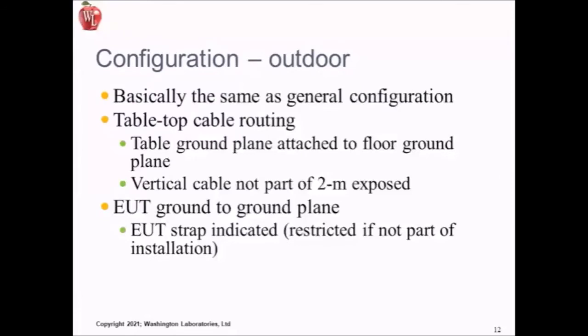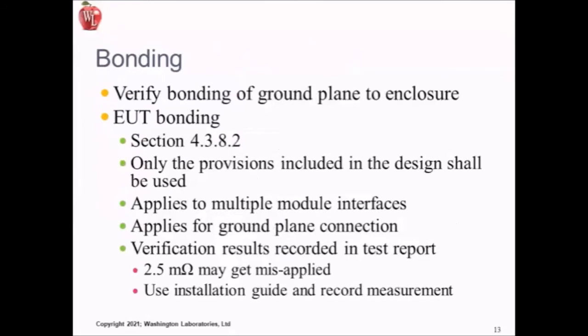So again, same as the general configuration. We've got the cables routed on the table. One of the things that you need to do when setting this up is verify the bonding of the ground plane to the enclosure. I mentioned that before. We try to get it below 2.5 milliohms. Section 4.382 has provisions for making that measurement. And you may need to make multiple connections in order to get that low impedance connection to the enclosure. You should record the measurement in the test report. Make sure that that's understood.